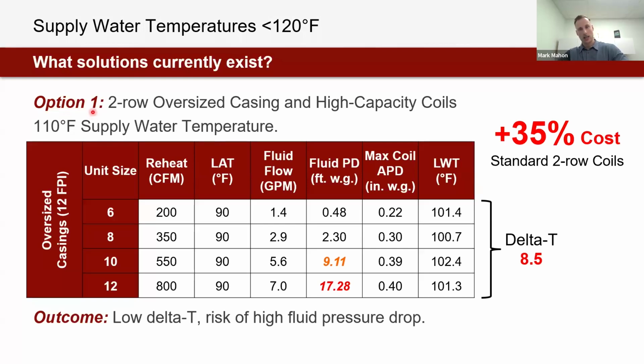Unfortunately, not good. In some cases, the performance isn't too bad from a fluid pressure drop perspective or from a fluid flow rate perspective. But for some of these larger boxes where we need more heat exchange and more capacity, we're starting to see fluid pressure drop creep up, GPM creep up. And the reality is the mean delta T for these coils is too low. An 8.5-degree delta T is not providing the coefficient of performance for the boiler we're really shooting for with this low hot water supply temperature target.